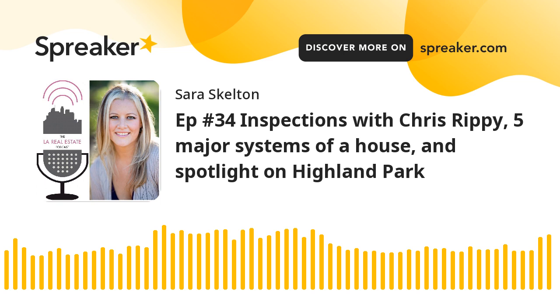With electrical, there's a number of things we look for, obviously. Now, we've got a number of panel manufacturers that we're on the hunt for. Both of you are very familiar with these names, of course, Zinsco and Federal Pacific, or FPEs, and of course the Stab-Lok, even some of the Bulldog Pushmatic breaker systems. And while some of them may have never been definitively determined to be defective, the problems with these panels are widely known, both to contractors, builders, and inspectors alike. So we're certainly on the hunt for that.